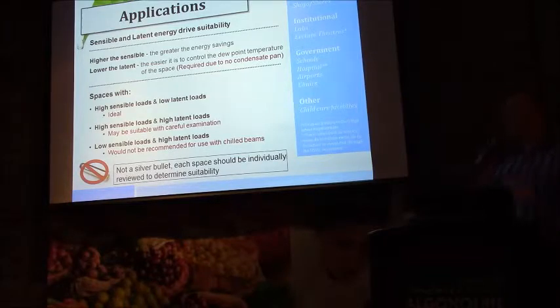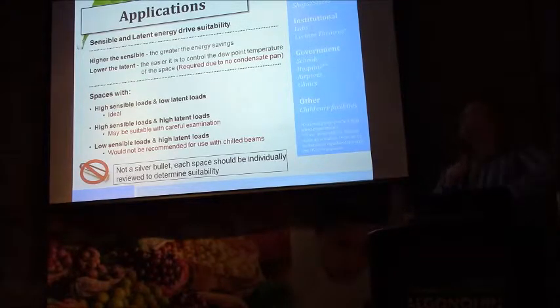And so these are some of the spaces that we might consider for active beams. Office spaces, data centers. Now, data centers in this context is really more of a desktop farm as opposed to a rack room, which has its own design criteria, and there's specialized equipment for that. Retail spaces, again, it can be a little more difficult to consider those spaces, not being able to predict the loading in the space. And labs for institutional, I'll pre-qualify that as dry labs. Wet labs that are driven by code air changes are pretty much off the table in terms of active beams for the space. But dry labs have been done, several of them.